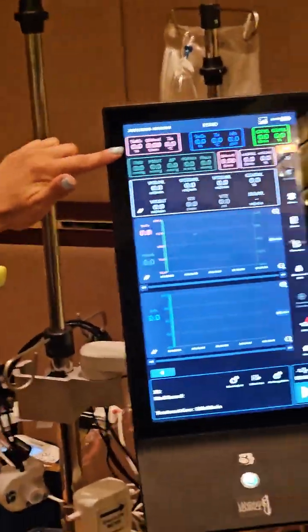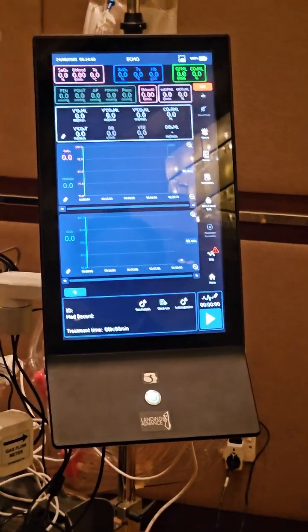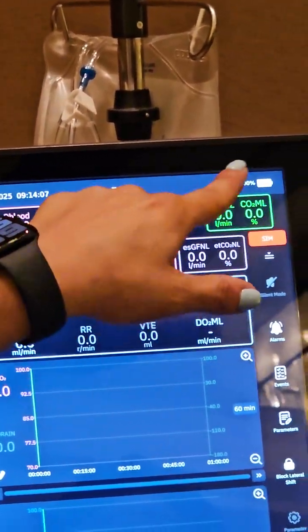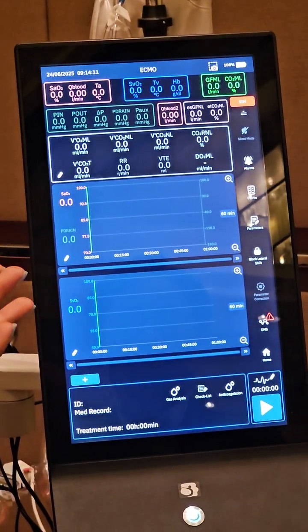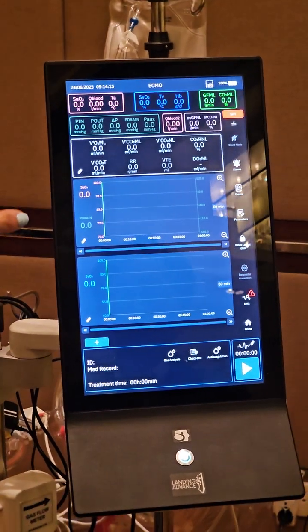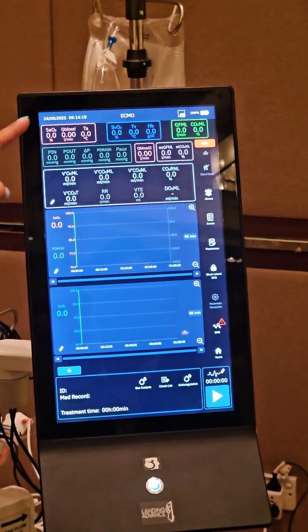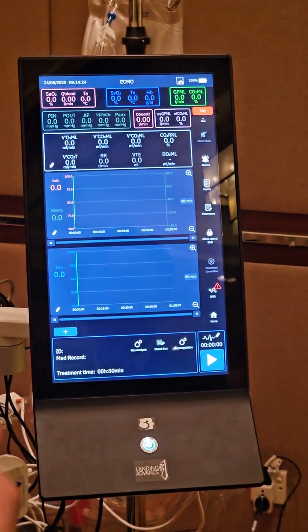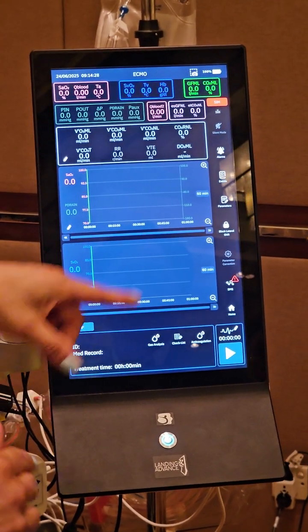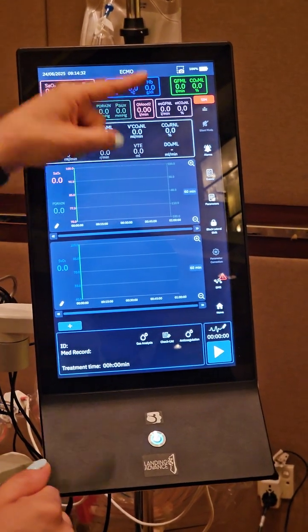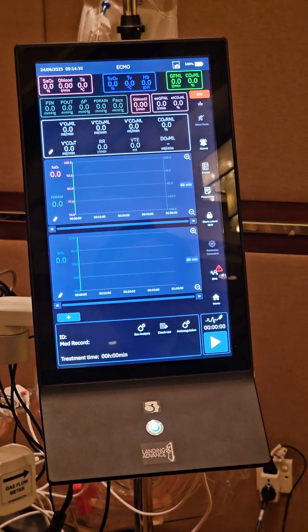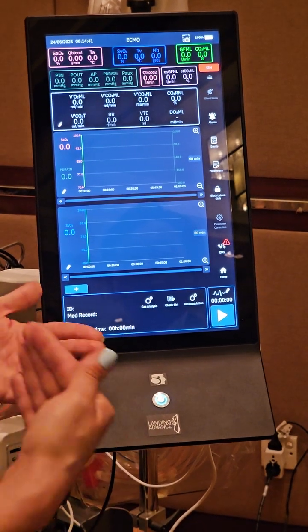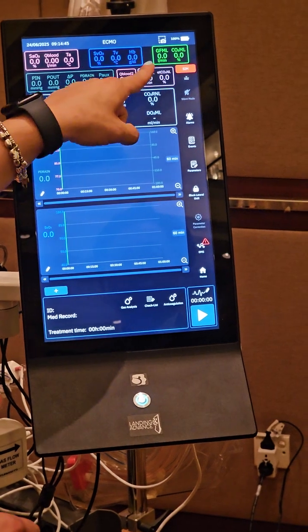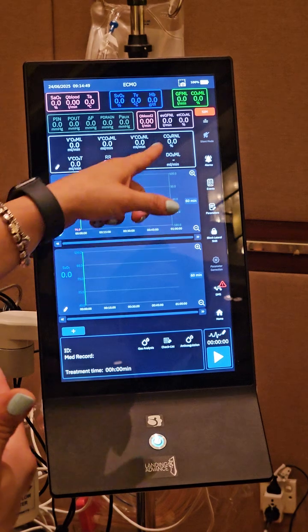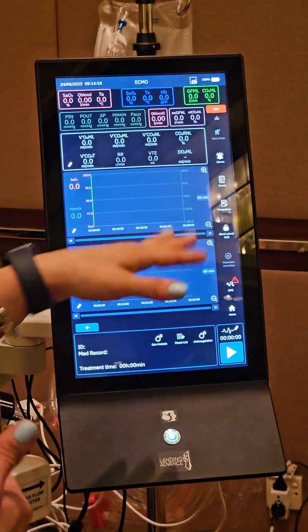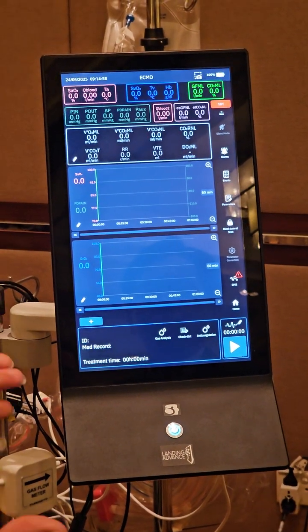So in each slot you will get 2 parameters. Starting from the top, you've got the measured parameters. It means arterial parameters, venous parameters, the parameters related to ML, which is membrane lung, so it means the oxygenator side parameters. You've got the possibility to connect the pressure transducers to have the pressures, as well as, we said, a secondary blood flow meter, so a secondary blood flow. And then you've got all the parameters related to the carbon dioxide, which are the ones that we need to check to evaluate the condition of the patient. So thanks to the patient side Landing Advance capnometer connected to the ventilator, you will get the exhausted carbon dioxide and gas flow from NL, which is native lung, so from our patient.